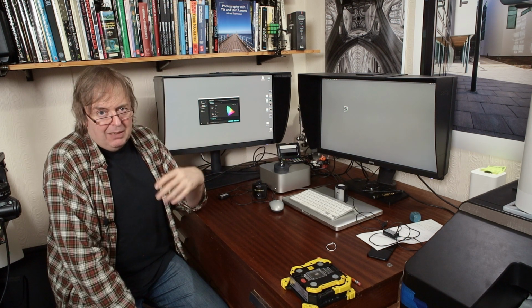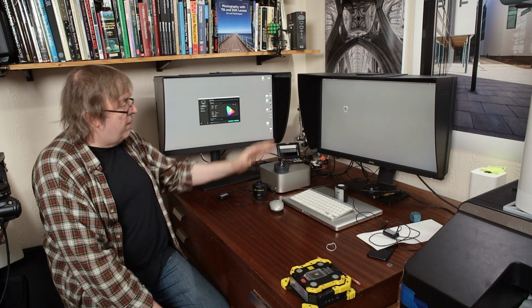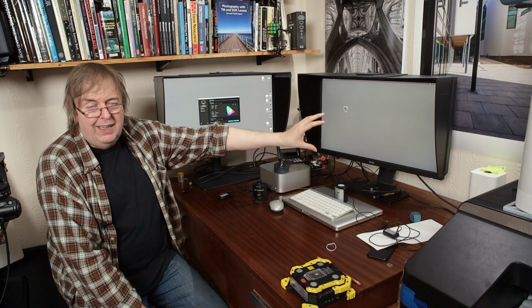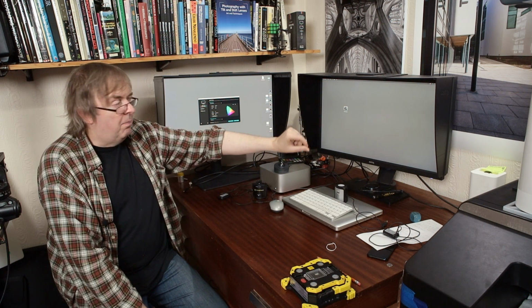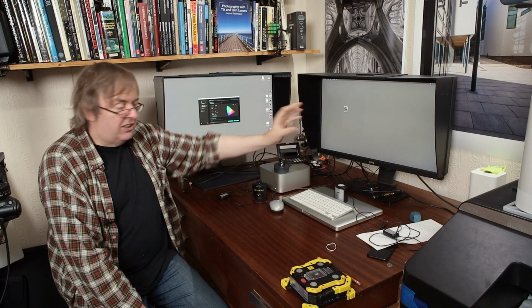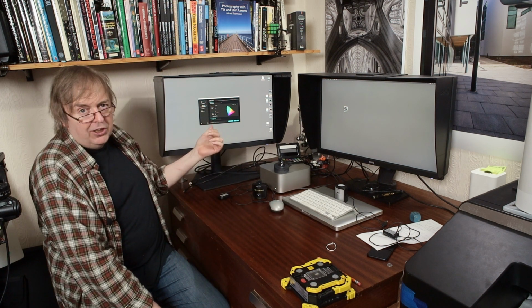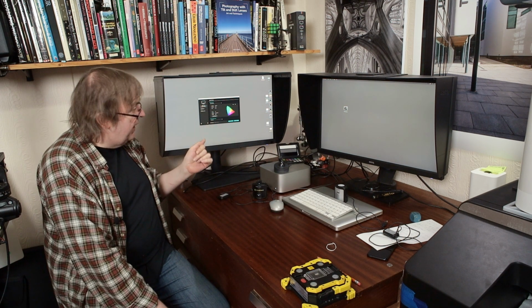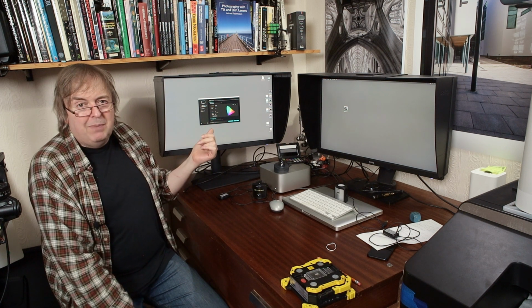Why hardware calibration? Because that takes the calibration aspects away from the computer and your graphics card, or however your graphics system is doing it. What it means is that the calibration is in the monitor. It's much more robust. It means that the display profile has much less work to do, and certainly if you've got a larger gamut screen like these ones here, it just makes for better looking displays.